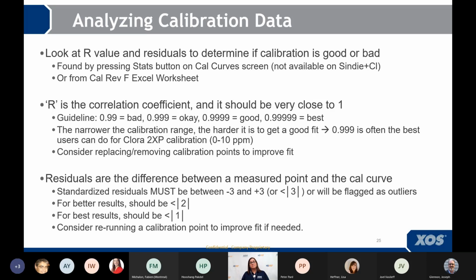The residuals must be between -3 and +3, or they get flagged as an outlier, in red in the previous slide, okay? But if you're really looking to maximize your calibration and have the best calibration possible, you want those values to be smaller. For better results, they should be between -2 and +2. But for the best results, you want to look for residuals that are between -1 and +1. And in order to do that, you would consider rerunning and replacing those calibration points as needed to improve your calibration.